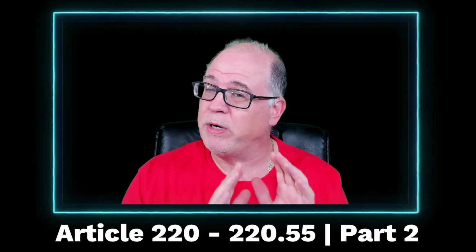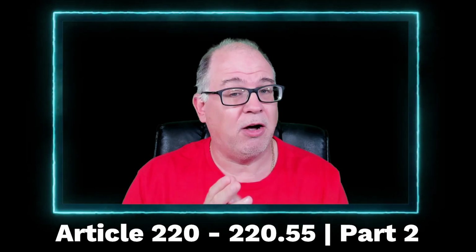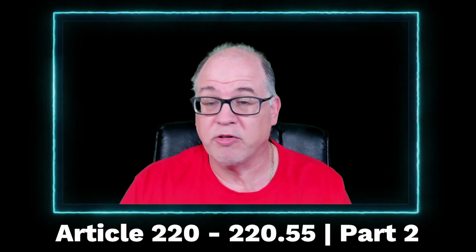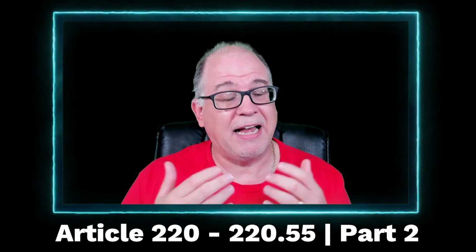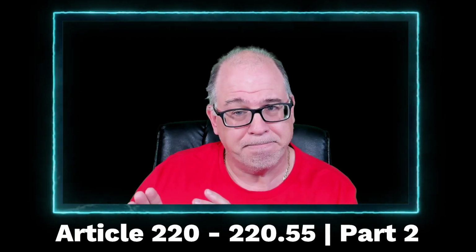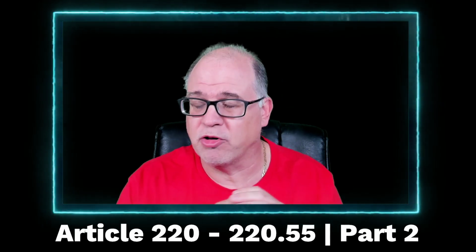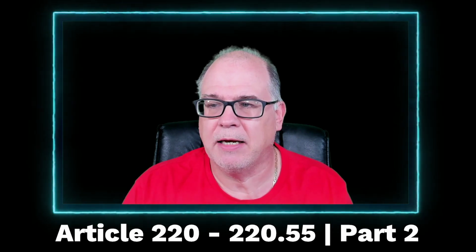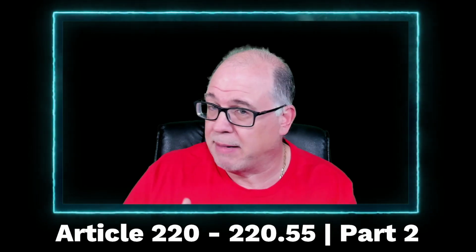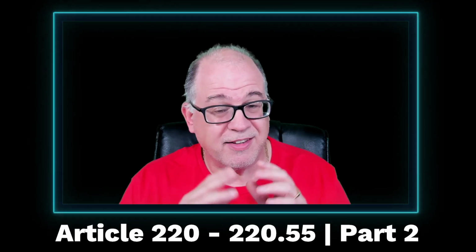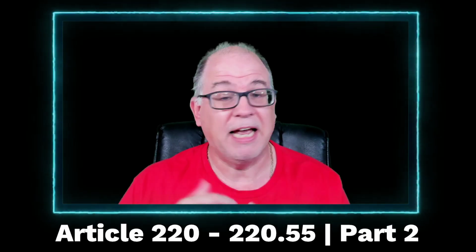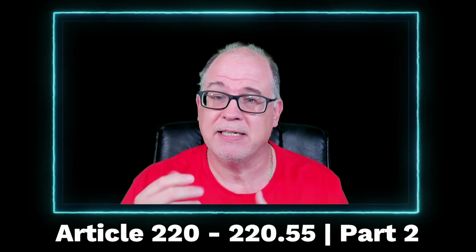Now, again, we talked about how to do branch circuits. In this part, we're going to get into calculating the loads using the standard method, which utilizes the 220.55 table. Remember, if it's the optional method, you just take the nameplate. If it's the standard method, you're going to use 220.55, and you might be using the standard method to size a feeder to an individual dwelling unit. You might be doing the optional method, but if you're using the standard method, you need to know all about 220.55 and the tables, as well as the notes underneath it.